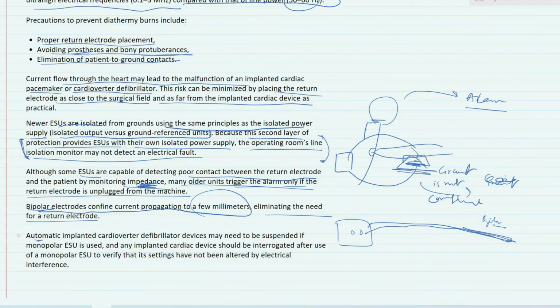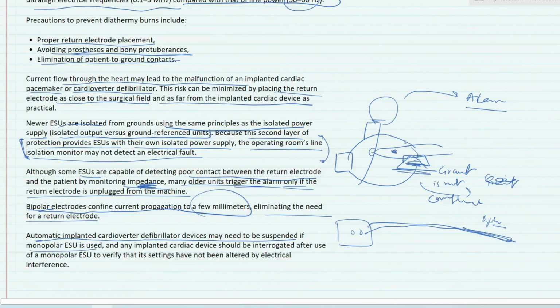So an automatic implanted cardioverter defibrillator device may need to be suspended if a monopolar ESU is used. Again, we know why it is, because of the potential of electrical current passing through it and then disrupting its function. And any implanted cardiac device should be interrogated after use of a monopolar ESU to verify that its settings have not been altered by electrical interference.